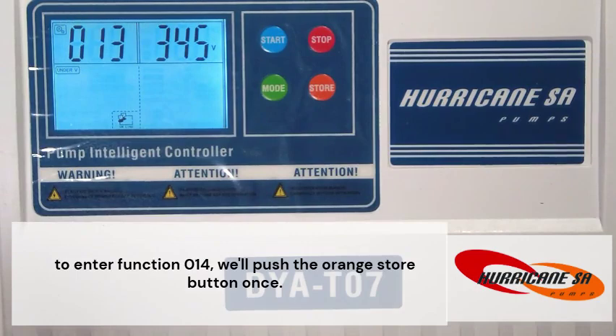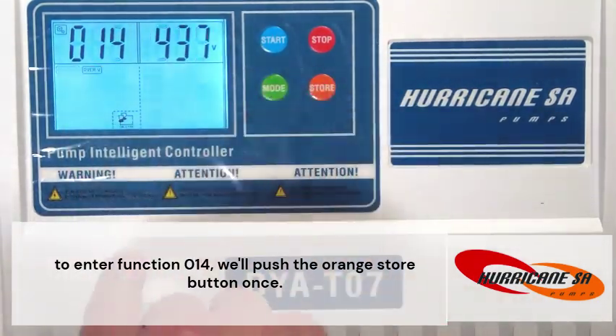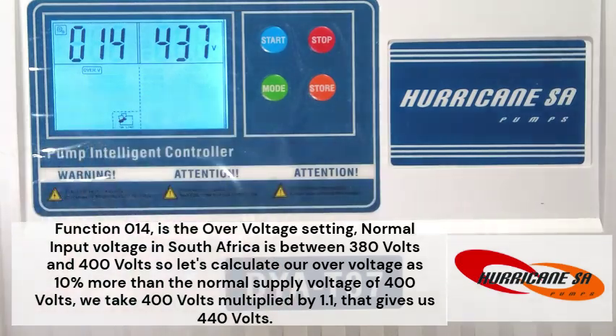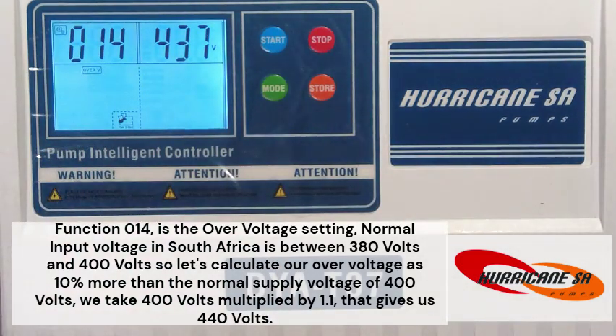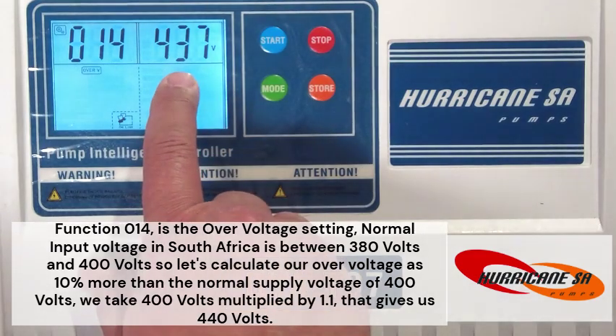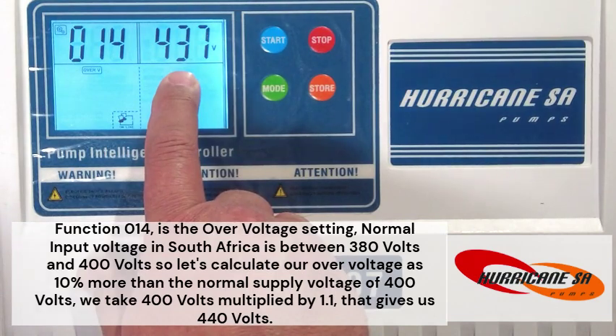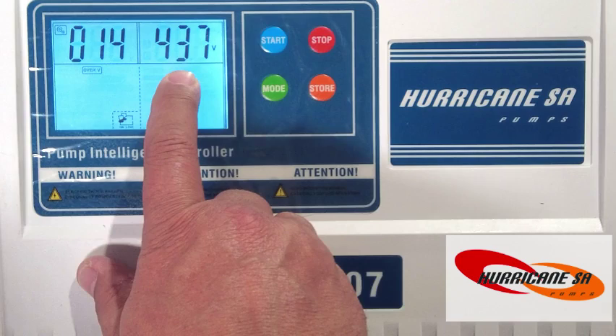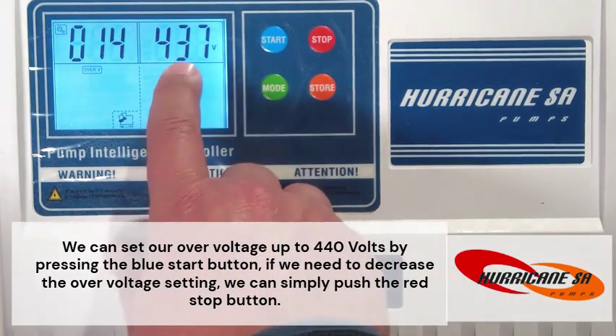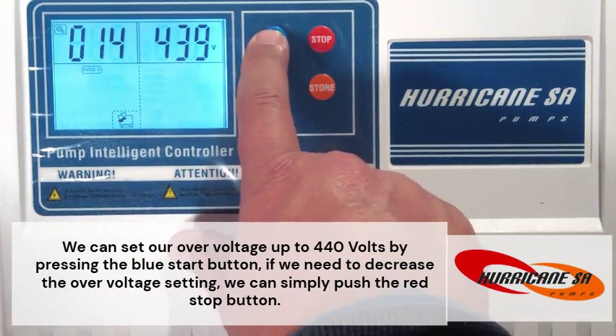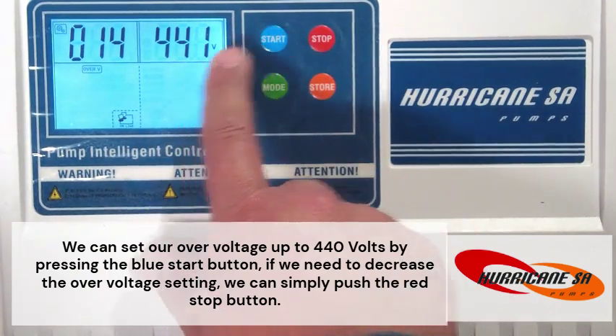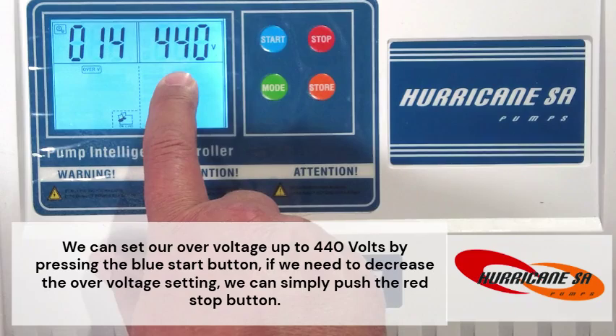To enter function 014, we'll push the orange store button once. Function 014 is the over voltage setting. Normal input voltage in South Africa is between 380 volts and 400 volts. So let's calculate our over voltage as 10% more than the normal supply voltage of 400 volts. We take 400 volts multiplied by 1.1. That gives us 440 volts. We can set our over voltage up to 440 volts by pressing the blue start button. If we need to decrease the over voltage setting, we can simply push the red stop button.